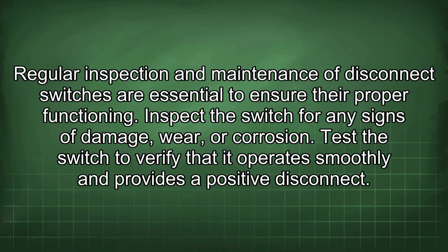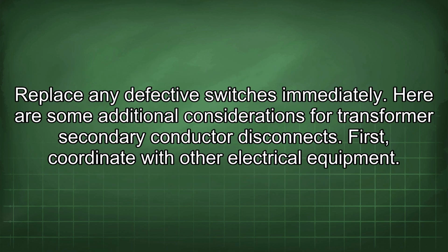Regular inspection and maintenance of disconnect switches are essential to ensure their proper functioning. Inspect the switch for any signs of damage, wear, or corrosion. Test the switch to verify that it operates smoothly and provides a positive disconnect. Replace any defective switches immediately.